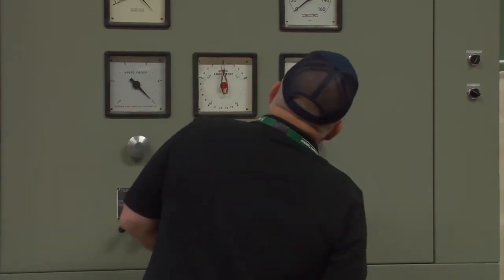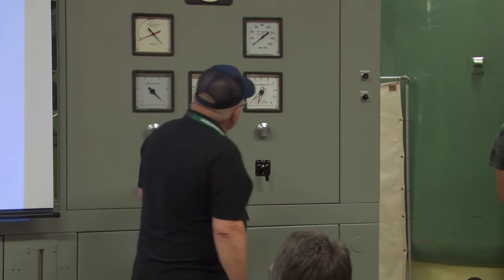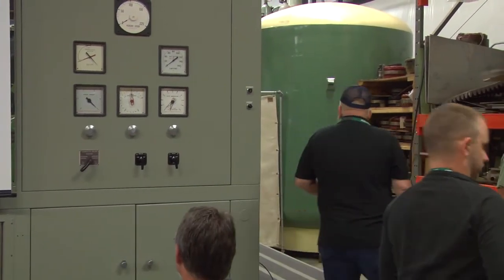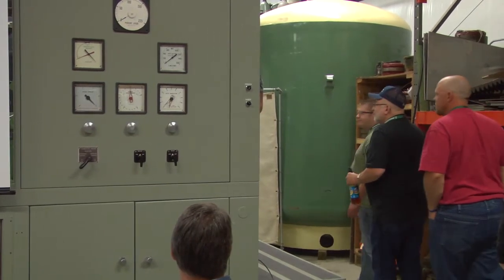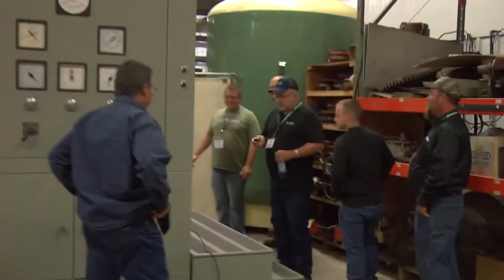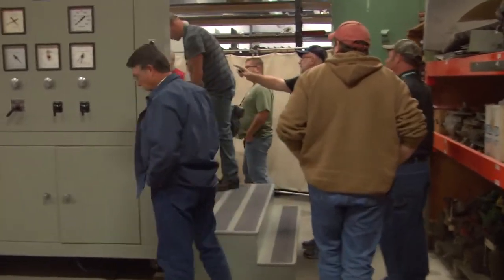You guys overhaul your units, you time them, you're done and everything, and record it to compare against last year. Yeah. Okay, so I got 2%. Do you guys want to get a wrench and see if you can get part of that out? We know we've got a problem on the stroke too. Okay, right. So we'll start with taking about 1% out of that, and it'll be on the cable end, right? Yeah, that's a special open-end adjustment. This would be the cable ends of the restoring cable.